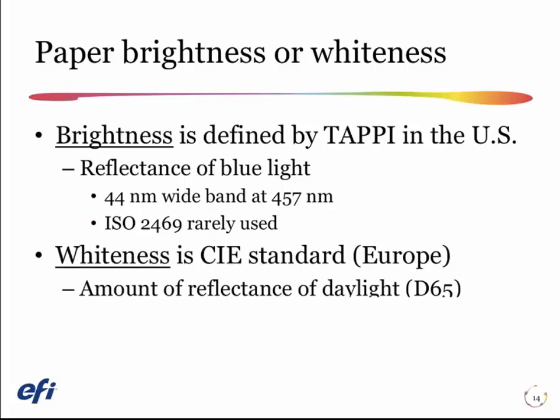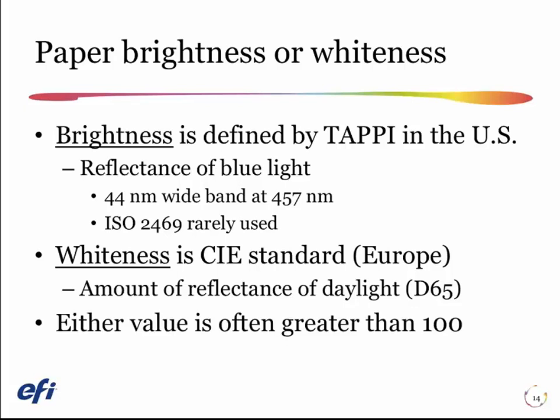Brightness ranges up to 100 in theory, but for a reason we'll understand in a few minutes, brightness values often go over 100. The other whiteness or brightness we need to understand is the whiteness defined by the CIE. This is the European standard, and this is the amount of reflectance, rather than of a single blue wavelength at 457 nanometers, of the entire daylight spectrum, the D65 spectrum. This has the same characteristics as brightness, though they're not one-to-one, so depending on where you're working, you might specify a paper as a certain brightness level or a certain whiteness level.